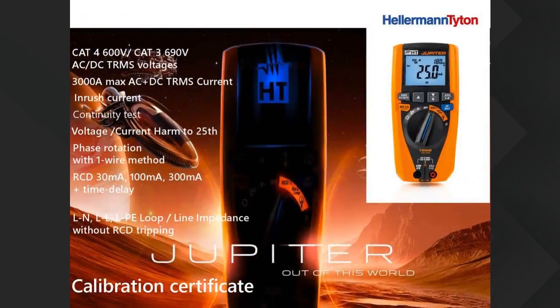So the next meter in the range is called a Jupiter. Now, when this meter came out, our supplier brought out a whole range of meters, and it's got specific names like Jupiter and so forth. You will see from other meters as well. And Jupiter is specifically a compliance tester. Now, guys doing compliance testing would know they need to measure prospective short circuit current, loop, earth leakages, phase rotation, voltages, and so forth. So this meter is basically designed to do that.